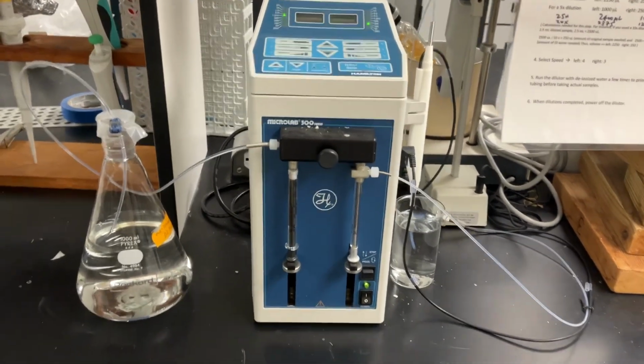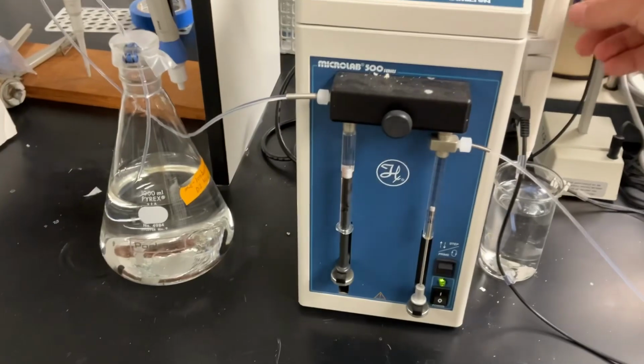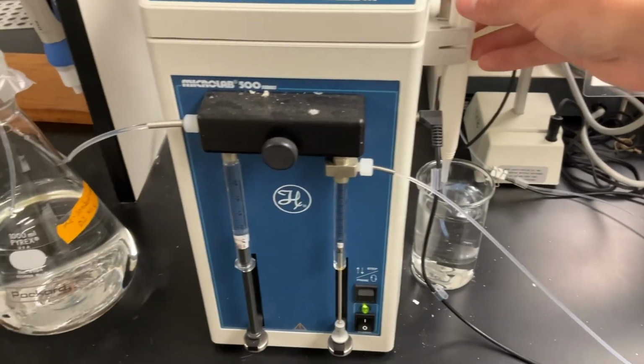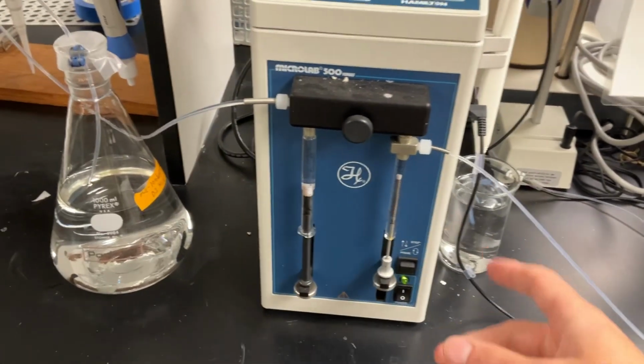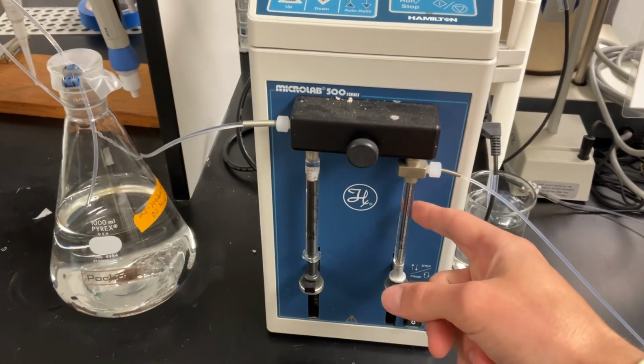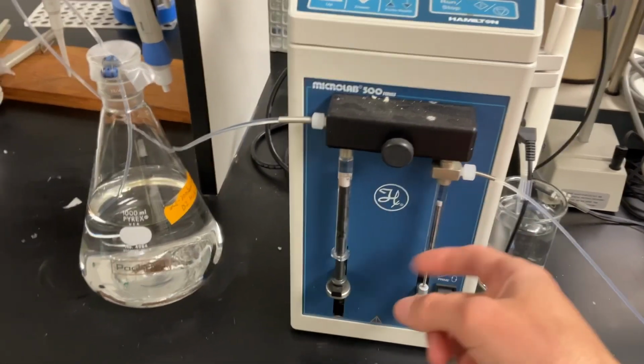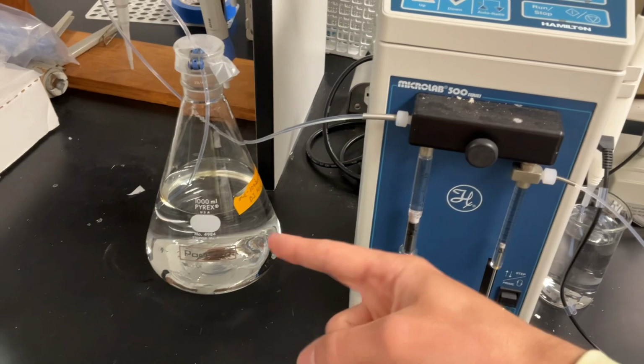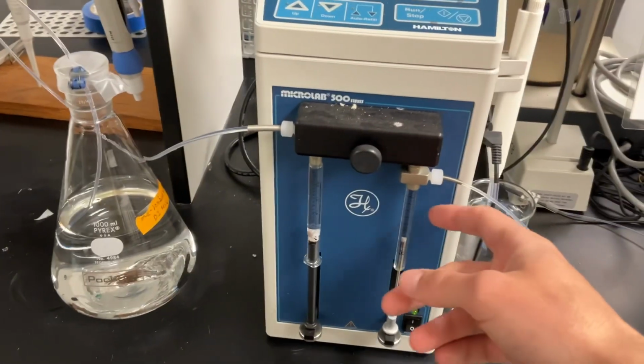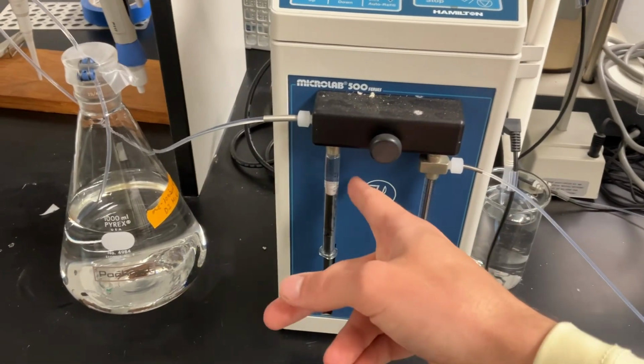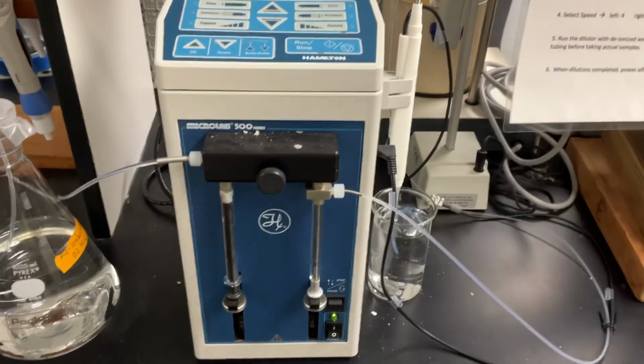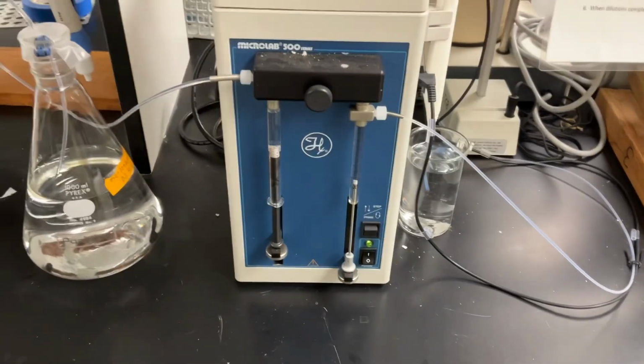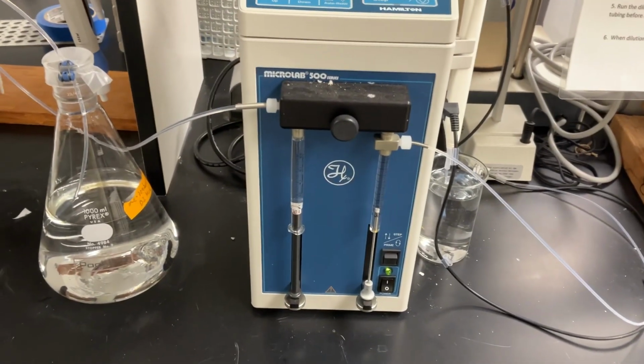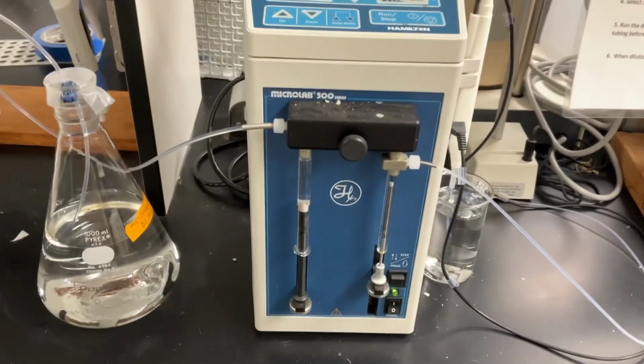And what this is actually doing, when I take this pen out and use it to dilute my samples, is it's going to remove a certain amount of sample fluid with this syringe, and then it's going to remove a certain amount of water through this syringe. And then it'll eject this syringe first, followed by this syringe, which ensures that all of the sample is removed, followed by a very precise amount of water, which allows for very, very clear, clean dilutions.